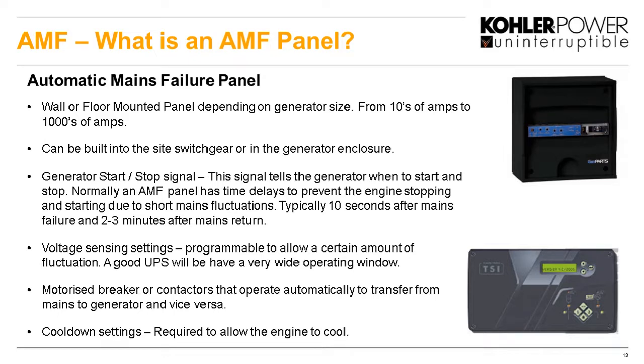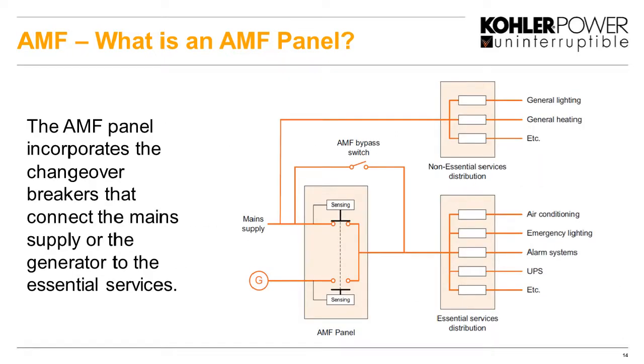And when the mains returns, again, it might not be stable. So there'll be a timer, and it's again programmable, that we will set and typically lasts for a couple of minutes to make sure that mains is healthy. And then once we're happy with the mains, we will transfer back from the generator onto the now healthy mains, to continue to supply the critical load. Now, also, once the generator has come off load, it does need to cool down, and this panel will do the cooling times to allow the generator to run for a required time to cool down before we actually turn it off. During that time, if the mains does fail, the generator is also still available to be transferred immediately back on.